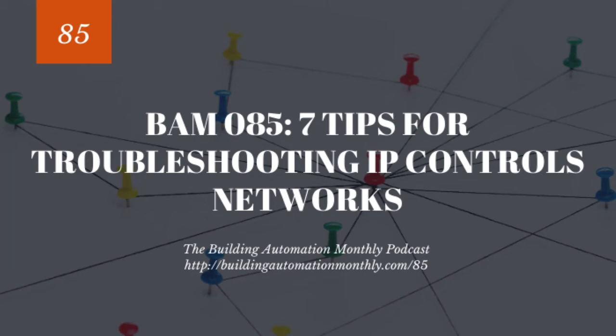Well, how I often will go about troubleshooting problems is I will start at the device that is having issues, and then I will follow it along the path to make sure that it is going wherever it's supposed to go. And then as soon as I see a deviation, that will help me pinpoint the potential issue.